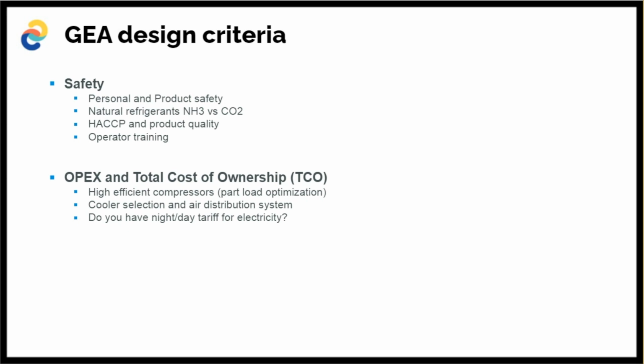The other thing, and it's been mentioned a couple of times this morning, is operating costs, OPEX, and total cost of ownership. We want to have highly efficient compressors, especially in part load. Because when installations are running in part load because the heat load is not calculated very well, the compressors are normally not running fully efficient. Then of course the right cooler selection and air distribution system. And we need to discuss what the tariffs for electricity are. Do you have a difference in night and day? Because this information also has a big impact on our heat load calculation. For instance, we could advise a customer to invest more in bigger compressors, but that they run less, and only in low tariff times, for instance.